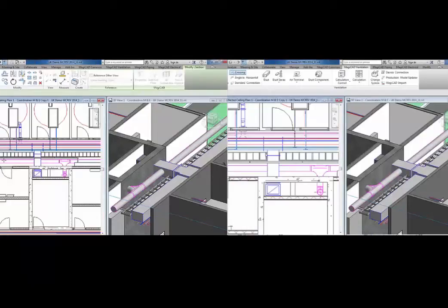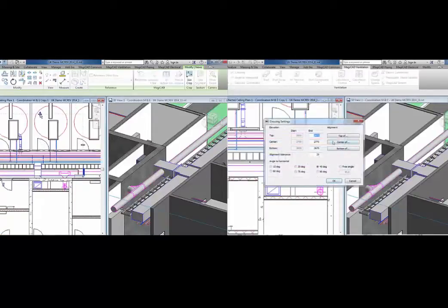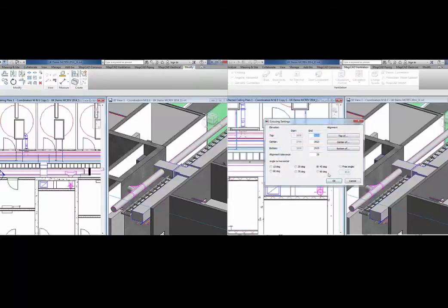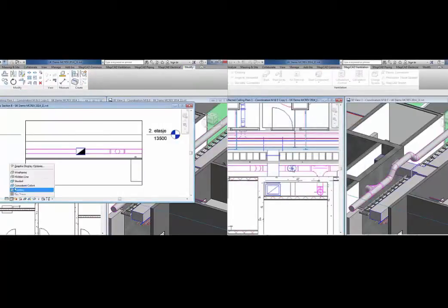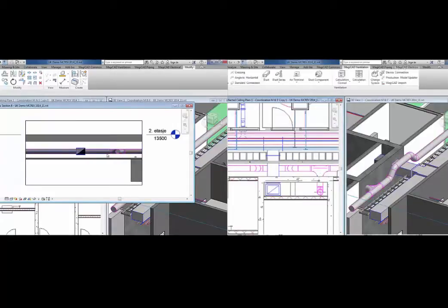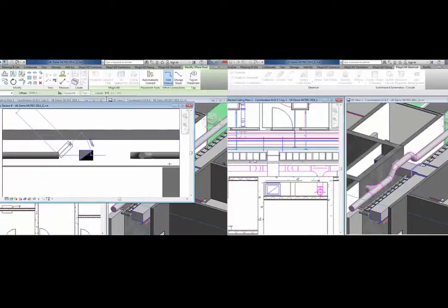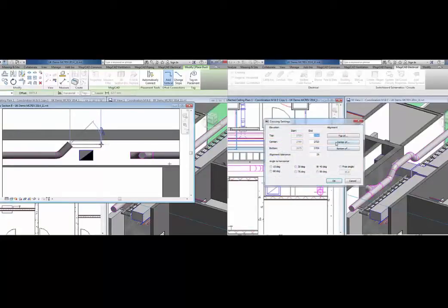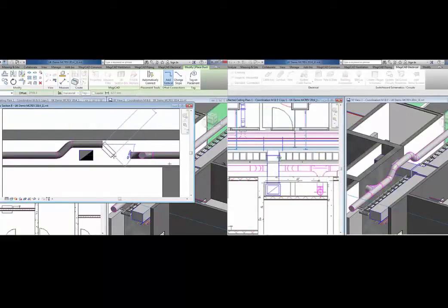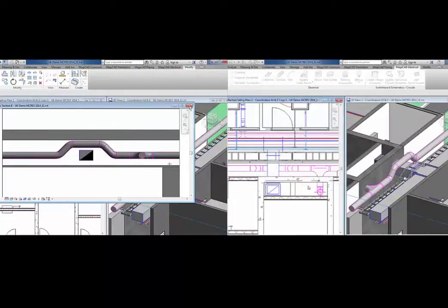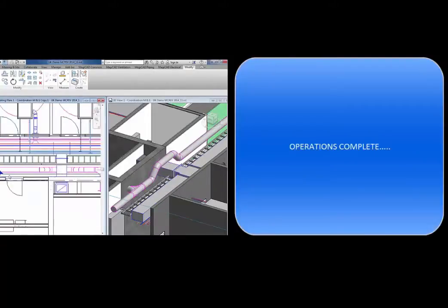This is the automatic crossing tool in MagiCAD. It saves a vast amount of time for technicians or engineers who wish to avoid clashes by rearranging the services once they have been put in. As you can see there on the right hand side, it's MagiCAD's functions which are just popping the offsets of cable tray and ductwork automatically over other objects at the specified heights in relation to each other, and with a tolerance between the services as defined by the user. And it's extremely quick and user friendly, and it's done.